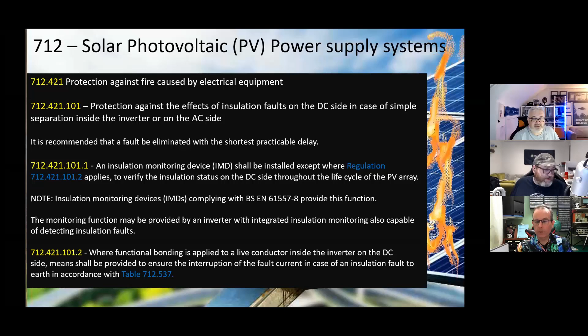This is Overcurrent 4.3. This is a minor introduction. So we've got here, with regards to the nature of the circuit, because obviously you can have a variety of different array configurations. In a PV array, where the number of strings is above 2 strings in parallel, protective devices shall be provided to protect each PV string where the following condition is met. So we have this little formula here, 1.35 times, and it's current.